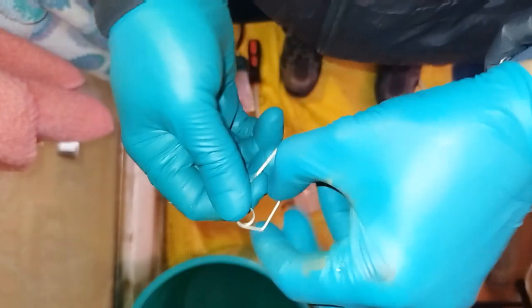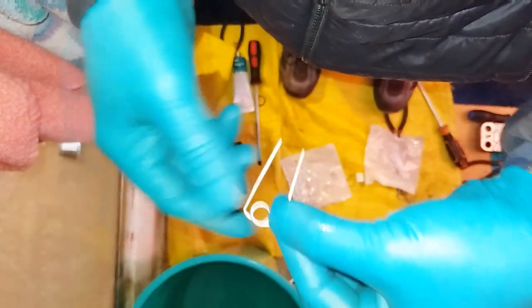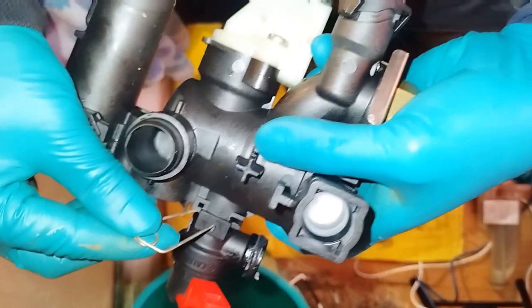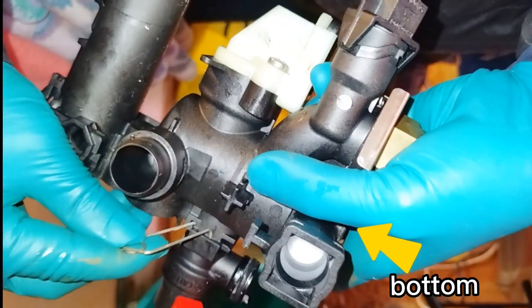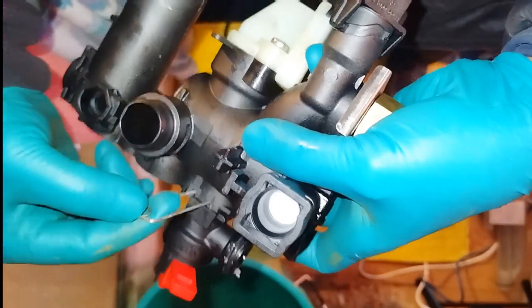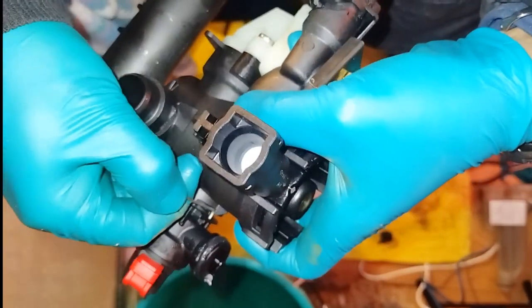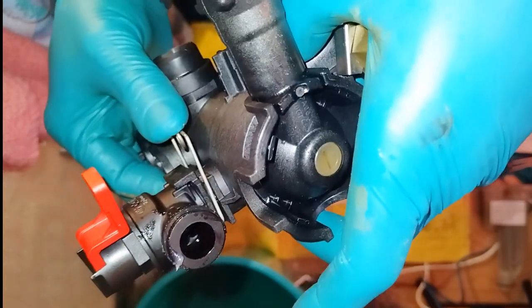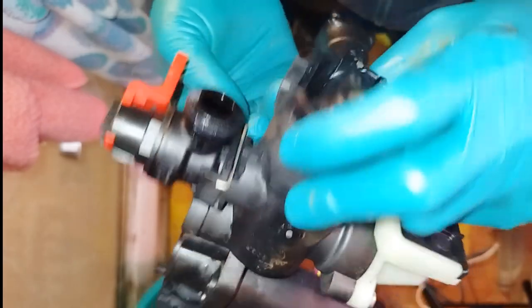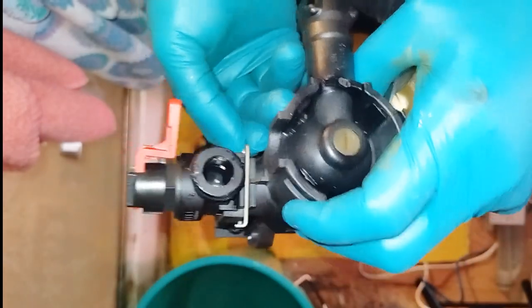You will need to slightly open it up or make the clip a little bit loose. This is how it goes in. The hand on the right is the bottom of the whole manifold, and this is if you look at it from the bottom, if it's fitted in the boiler. This is how this clip goes in, and the little locking mechanism on the clip stops the clip from coming out, hence it keeps the PRV in position.